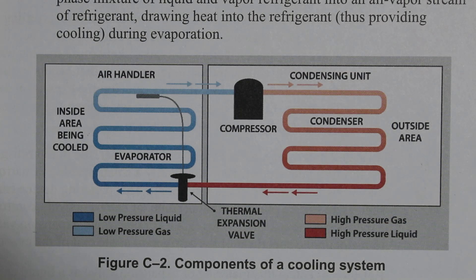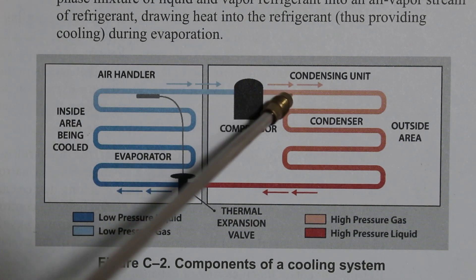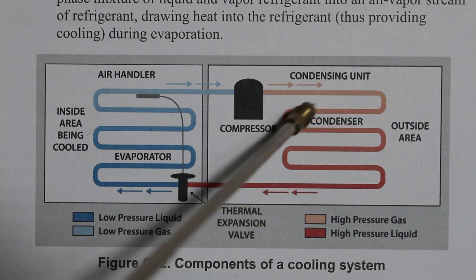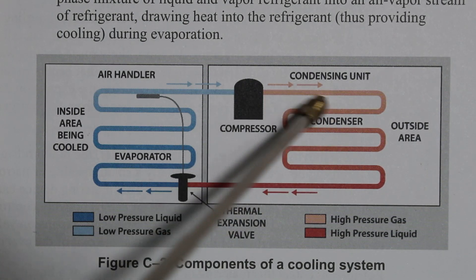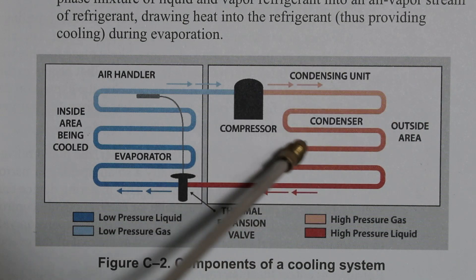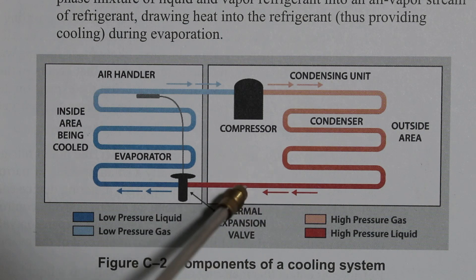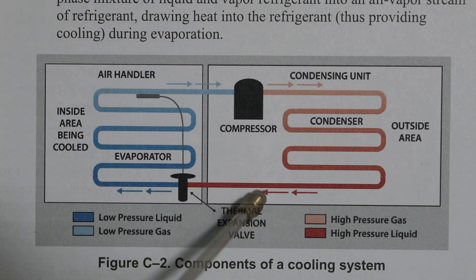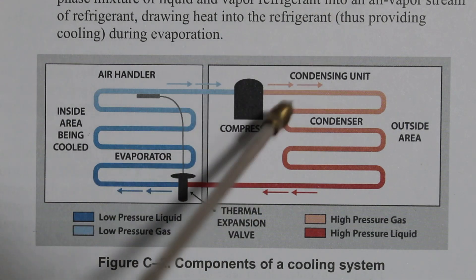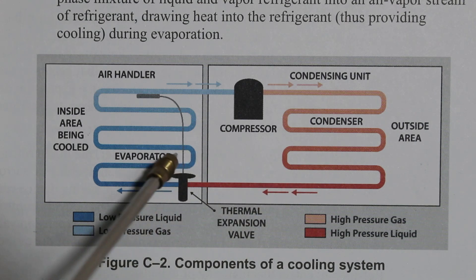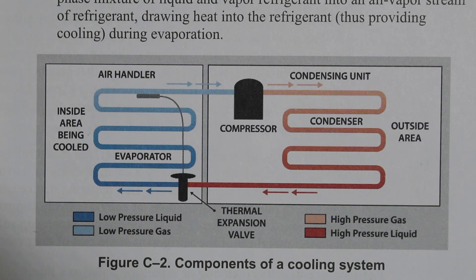Now that we know the state of the refrigerant entering and leaving the condenser, it's also important to note the names of the pipes. The pipe leaving your compressor and entering your condenser is known as your discharge line. The pipe leaving your condenser and entering your metering device is called your liquid line. Refrigerant then continues the path and we enter our third major component — the metering device.